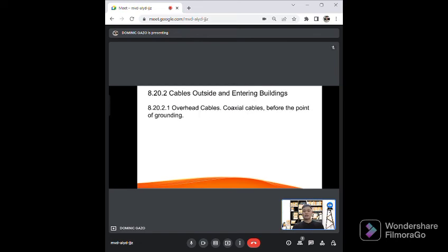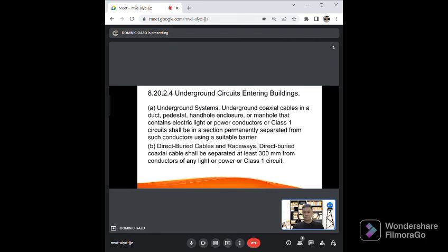For cables outside and entering buildings, overhead cables, coaxial cables before point of grounding. For underground circuits entering buildings, these underground systems, coaxial cables in a duct, pedestal, handhole enclosure, or manhole that contains electric light or power conductors, or Class 1, shall be in a section permanently separated, and for direct buried cables and raceways, it is not less than 300 mm from conductors of any light or power.